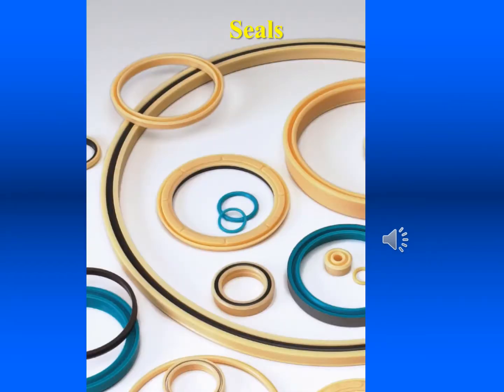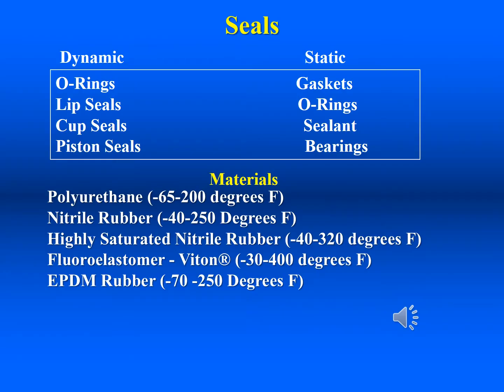Seals prevent the escape of fluids in systems and allow for full control of the fluid. They are made from a wide range of materials and are selected according to the environmental conditions. Seal technology has come a long way in the last 50 years, and we now have a seal for almost every imaginable application. Seals may be divided into two main categories. Seals that must control fluids as they move or between moving parts are dynamic seals. Seals that are trapped between parts that do not move are called static seals. The most common static seals are O-rings and gaskets.